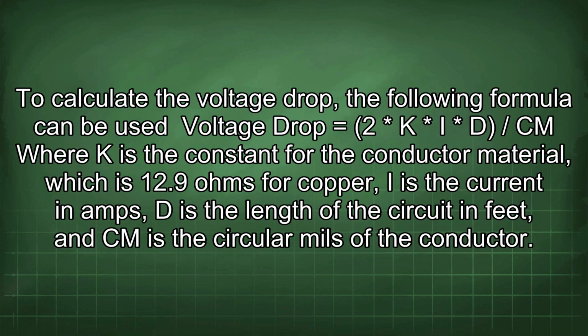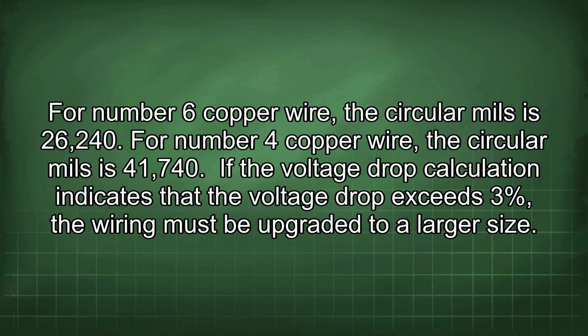To calculate the voltage drop, the following formula can be used. Voltage drop equals 2 k I d / cm, where k is the constant for the conductor material, which is 12.9 ohms for copper, I is the current in amps, d is the length of the circuit in feet, and cm is the circular mils of the conductor. For number 6 copper wire, the circular mils is 26,240. For number 4 copper wire, the circular mils is 41,740.